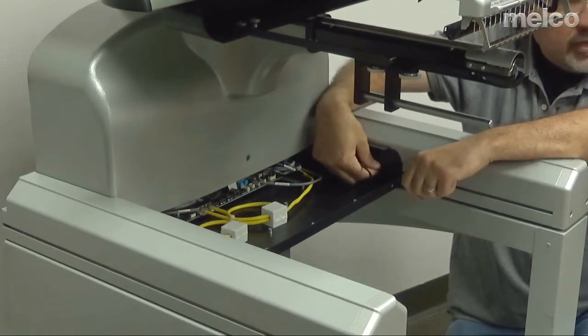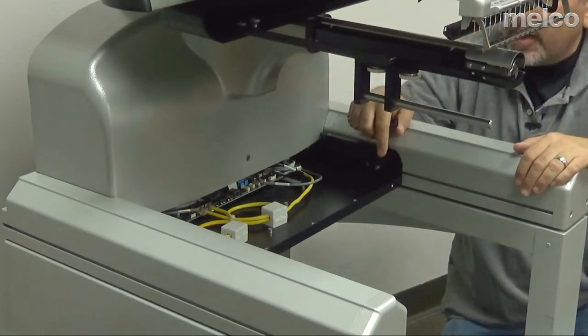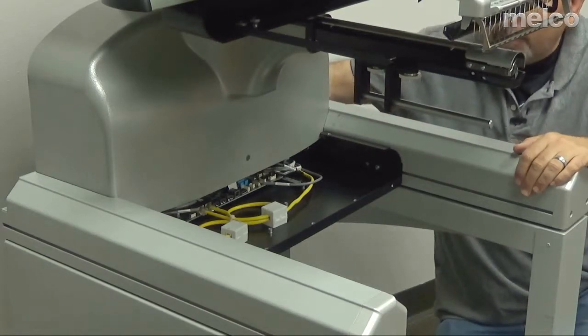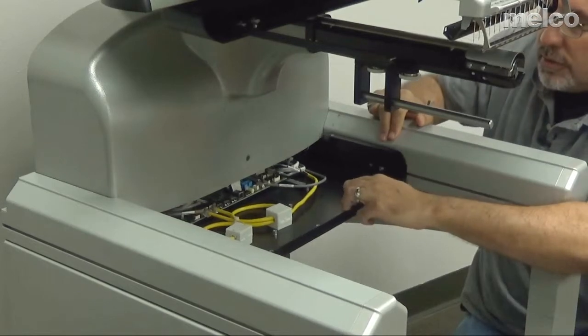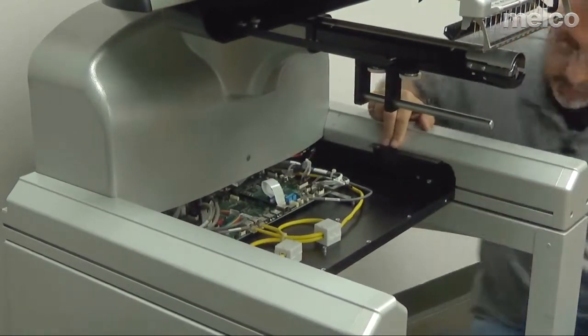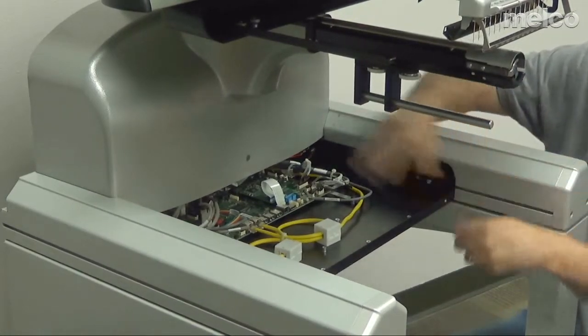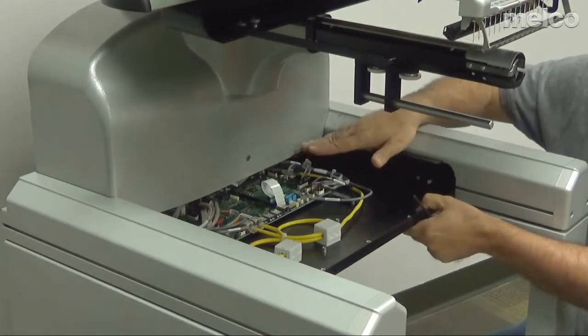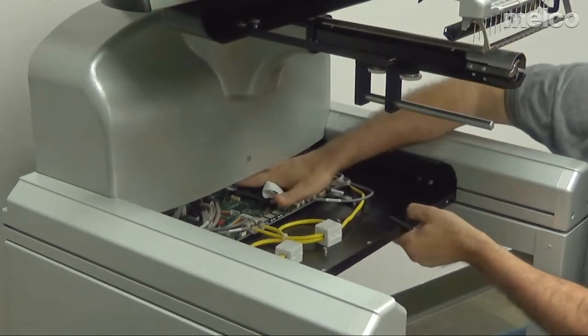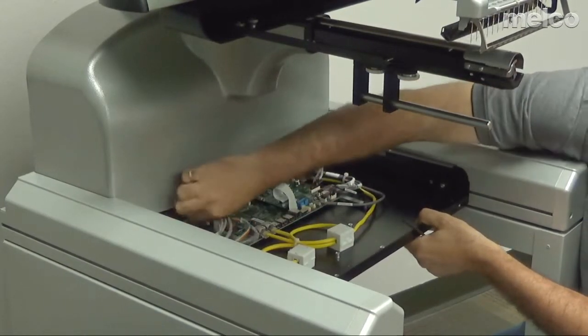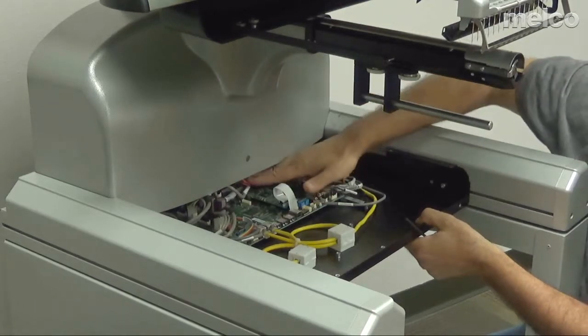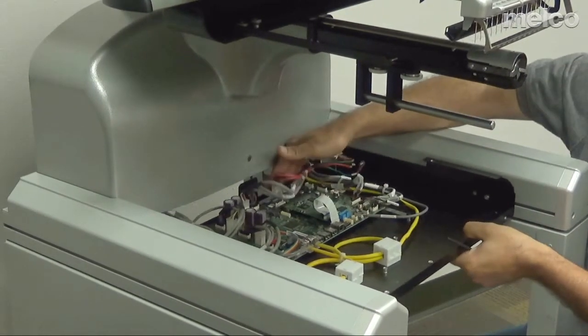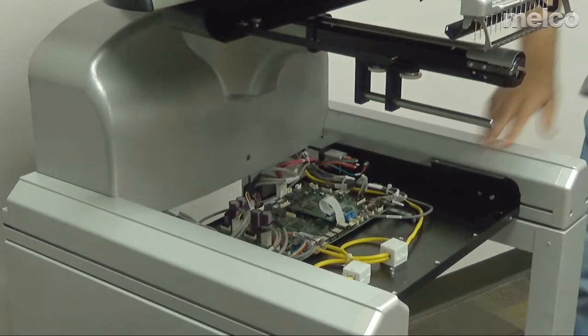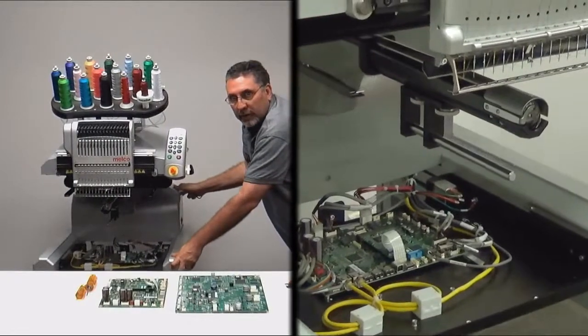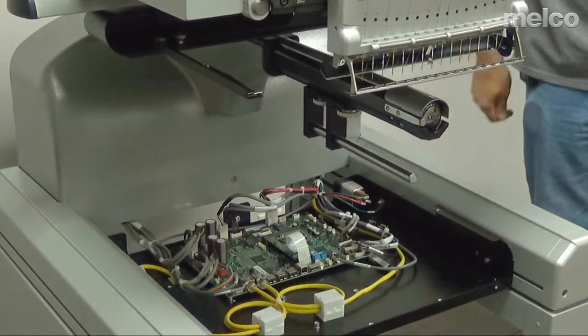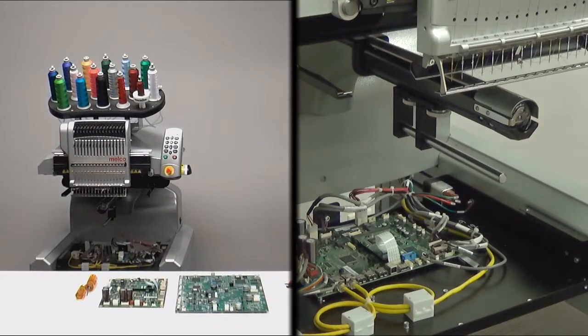So I have these 2 locking screws that are on the right and the left side loose now. I have the button head Allen screw out of the back. That's going to allow me to slide this tray forward. Now when I'm sliding this tray forward, there are a lot of harnesses that are connected to this main board. So we want to make sure that we're pulling forward slowly and that we're sliding our hand under there and we're getting all of these harnesses free so that they are not getting snagged on anything. And now you can see, I'll turn this a little more this way, now you can see we have full access to our main board of the machine.